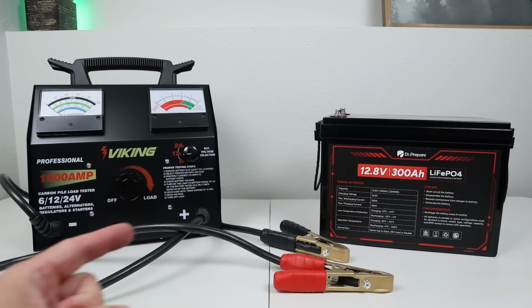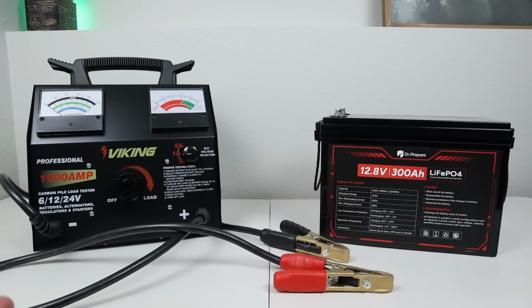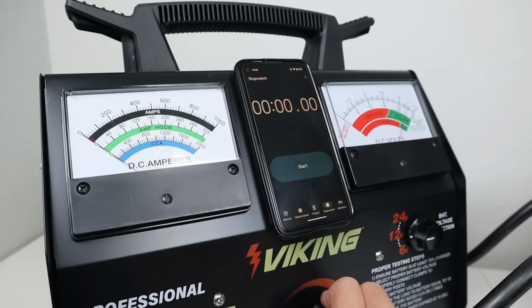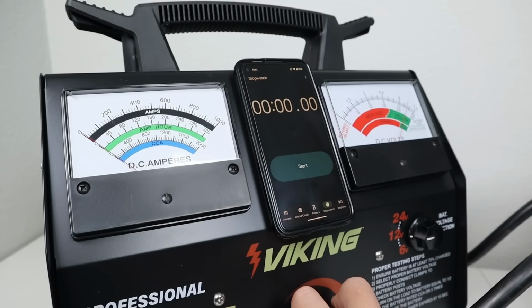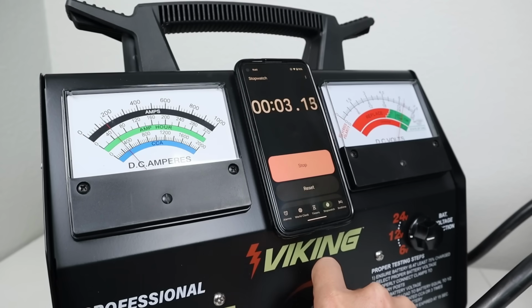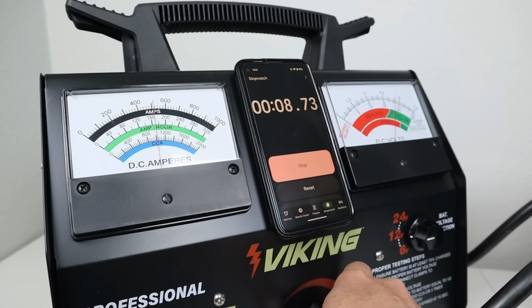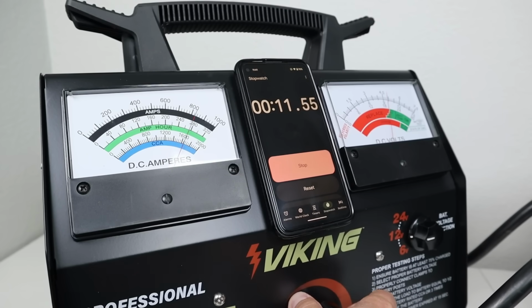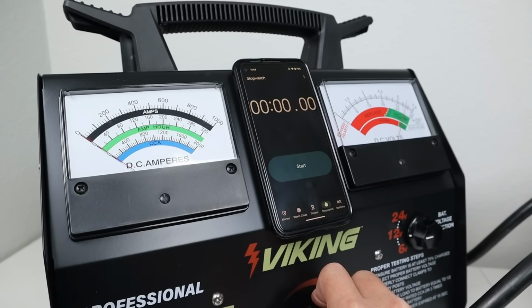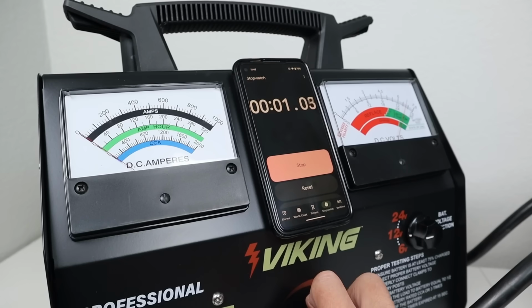Now in my next test, I want to see how many amps the BMS will allow before it shuts off the battery. In order to test that out, I'll be using my 1000 amp carbon pile load tester. Now if you remember, the BMS is good for 200 amps continuous, so I'm going to slowly turn up the amperage until the BMS shuts off. So let's see what happens here. 100, 200, 300, 400, 500, 600, 700, 800, and it didn't shut off. So let's go ahead and do this test one more time. I'm going to be a little bit faster just to see if that will trigger the overcurrent protection. So let's go ahead and start it. We're going to go quick.